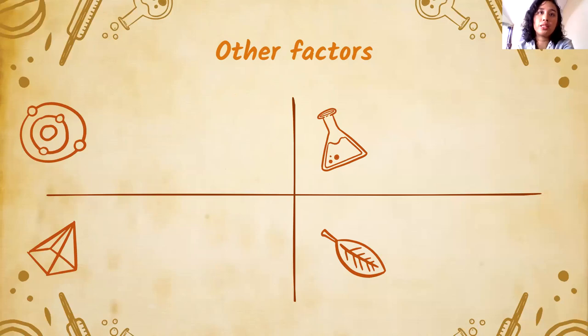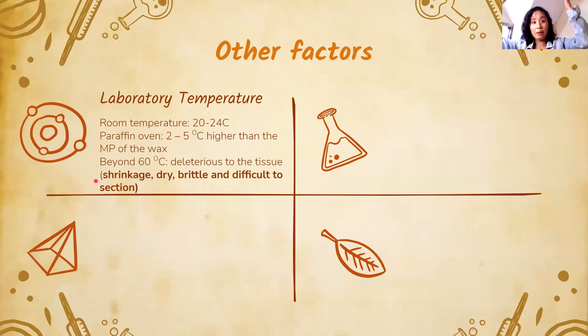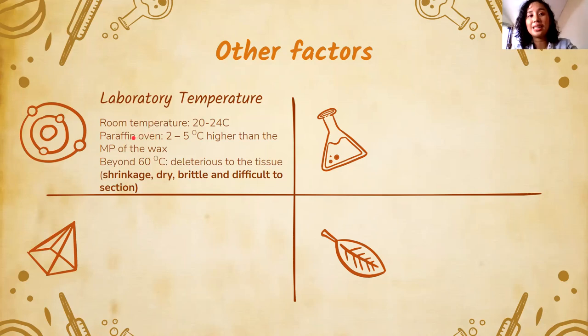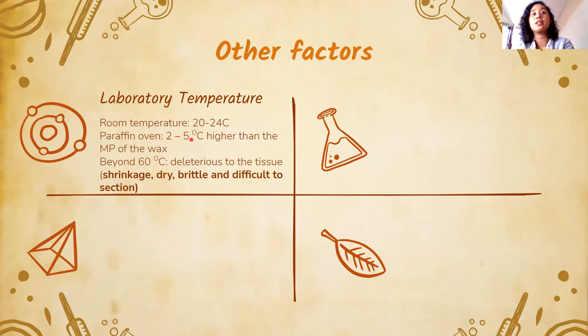Factors that affect embedding: laboratory temperature should be at room temperature. The paraffin oven temperature is very crucial. You must follow the manufacturer's recommended melting point. Usually the paraffin oven is set 2 to 5 degrees Celsius higher than the melting point of the wax. If the melting point is 56°C, set the oven to 58–61°C. Do not exceed the manufacturer's recommendation significantly.